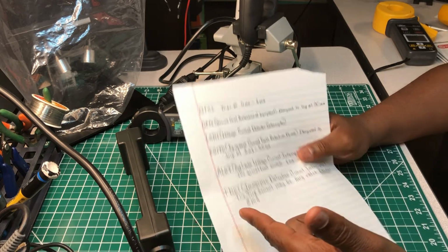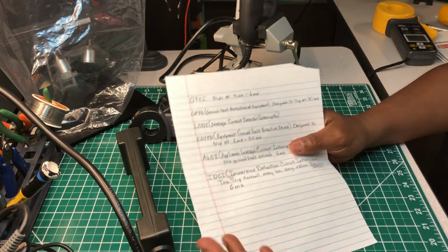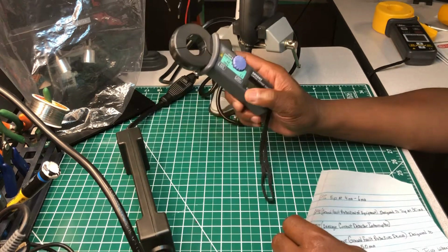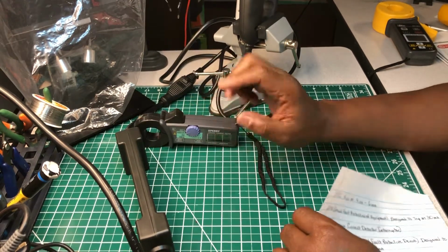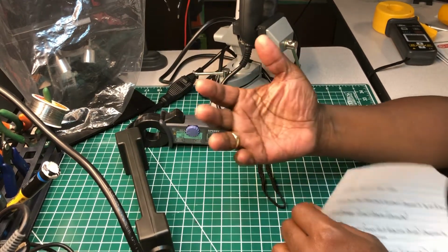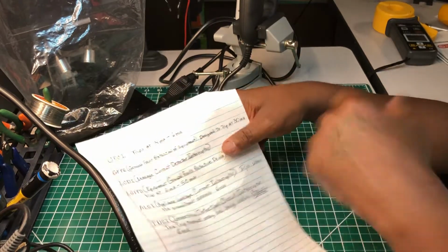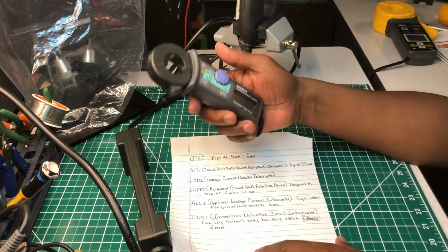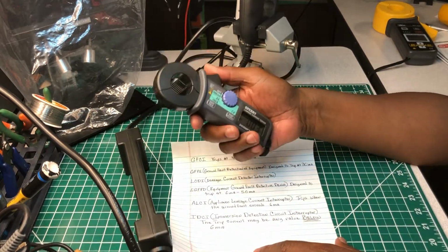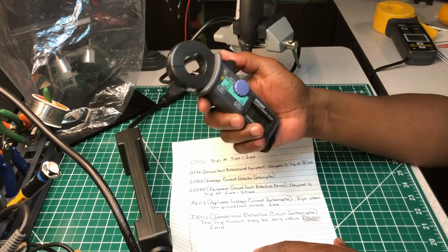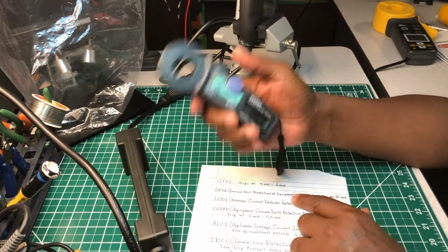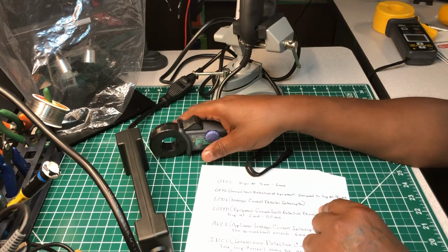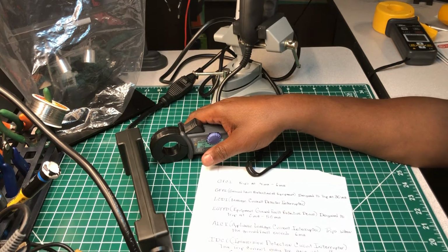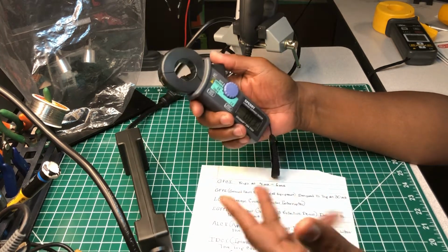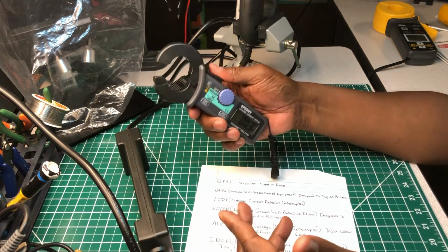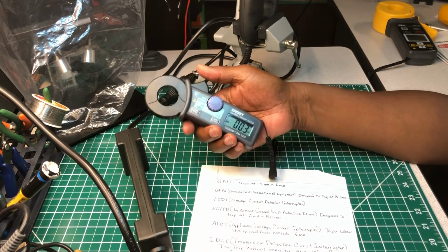And the only way you can figure that out by troubleshooting is if you had one of these testers right here. You can either check at the outlet by pulling the receptacle out. You wrap this around the neutral and the hot, the line and the neutral at the same time, and get a reading. Or you could go to the distribution panel and do the same thing. You can get the line and the neutral and put this around both of them and get a reading.